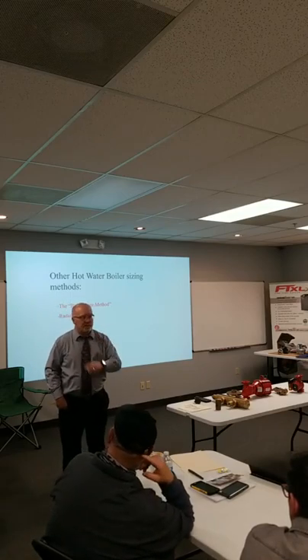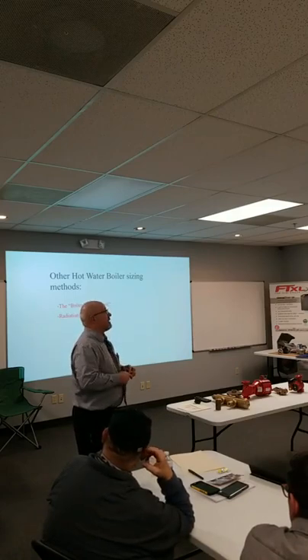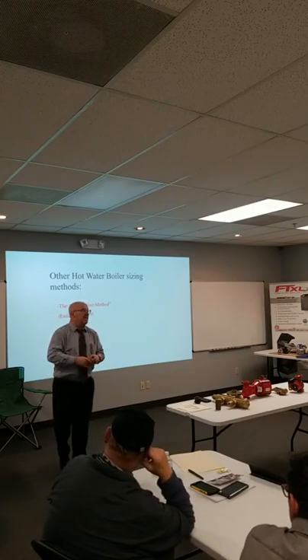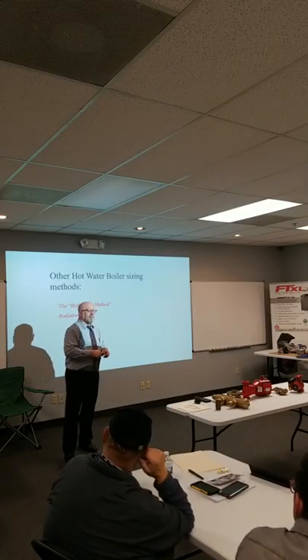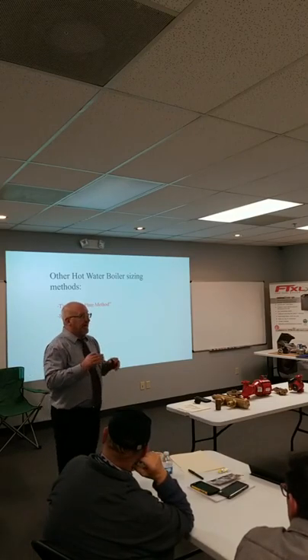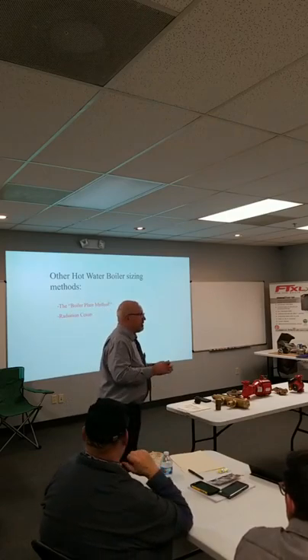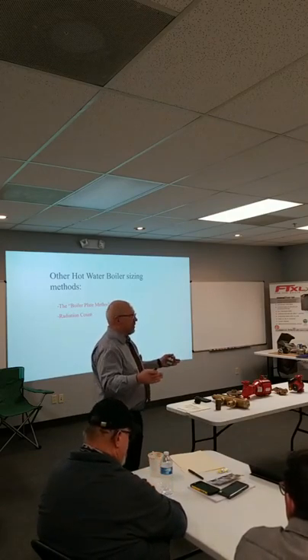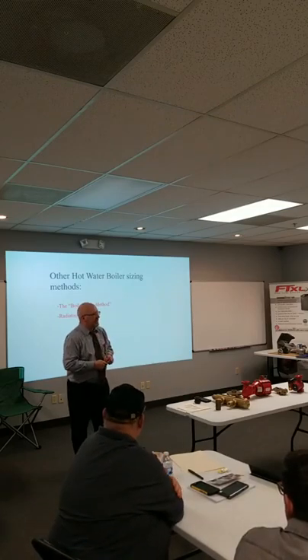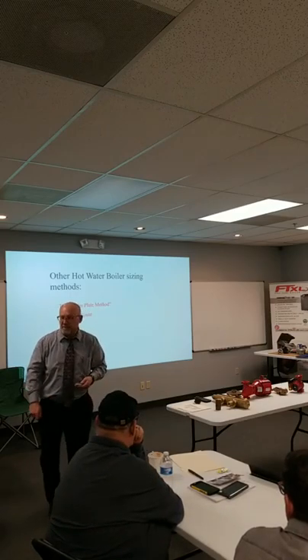What if you undersize a steam boiler? Runs and runs and runs and never makes enough pressure. Never makes enough steam. Works okay until you really need it because it's cold, really cold out. Yeah, a lot of times those problems, and we'll talk about hydronics too, a lot of times the problems by undersizing or changing a pump and maybe putting the wrong pump in, you don't see the problem in the shoulder weather, you only see it when it's really, really cold. And who wants to go out when it's really, really cold? Well, you guys do, because you make more money that way.